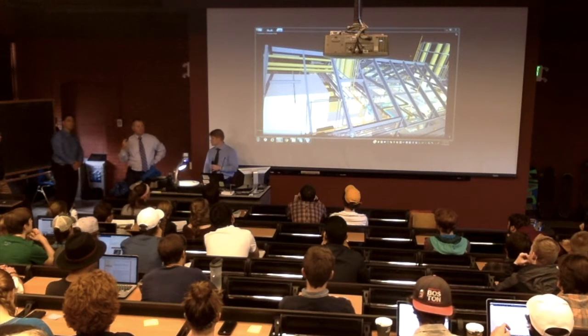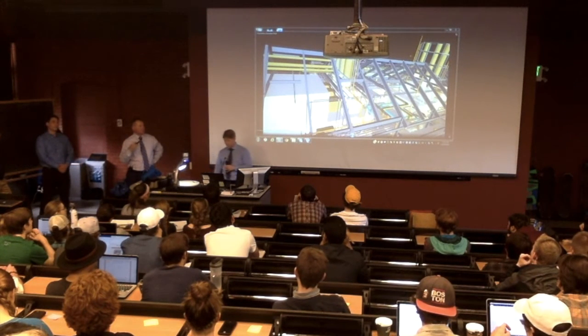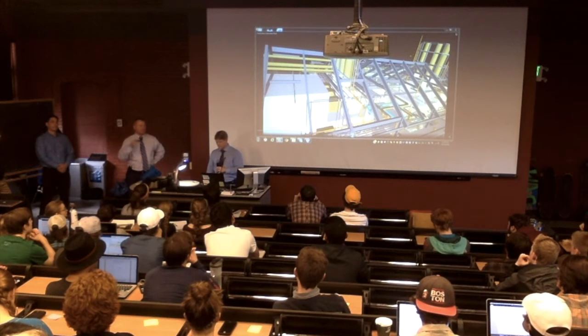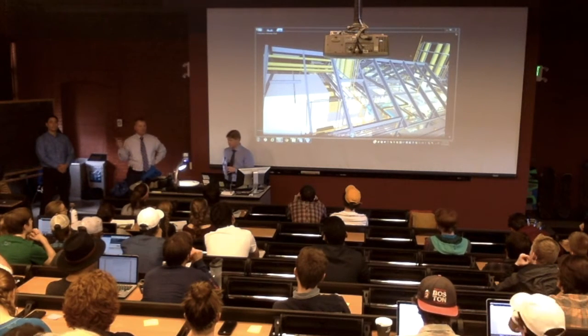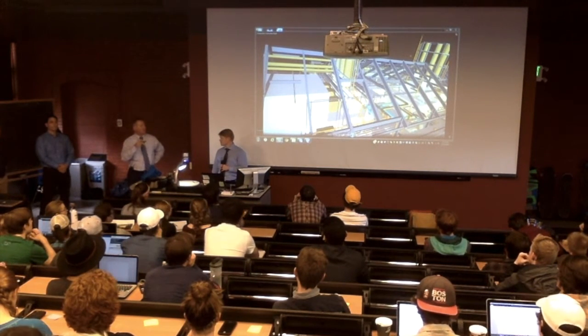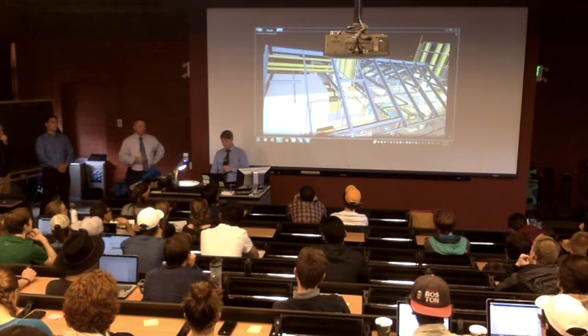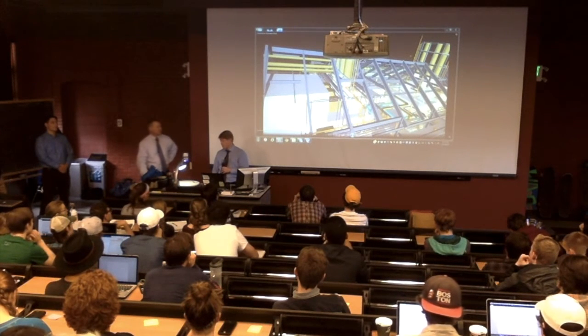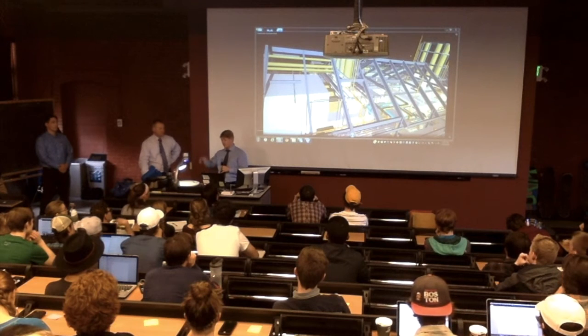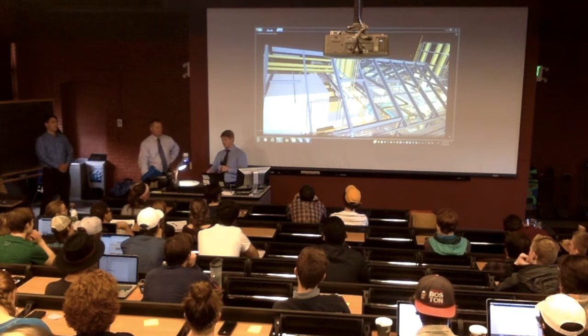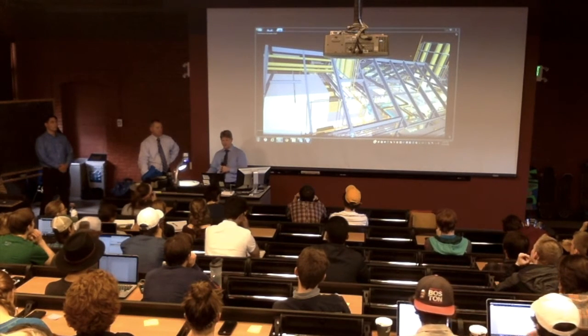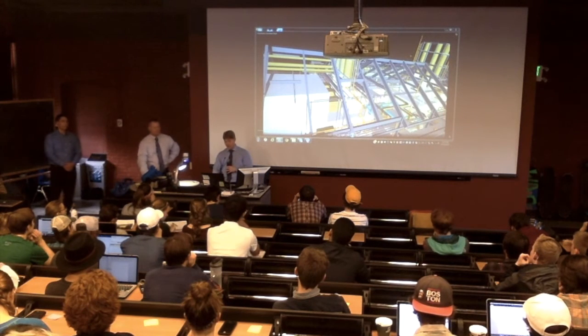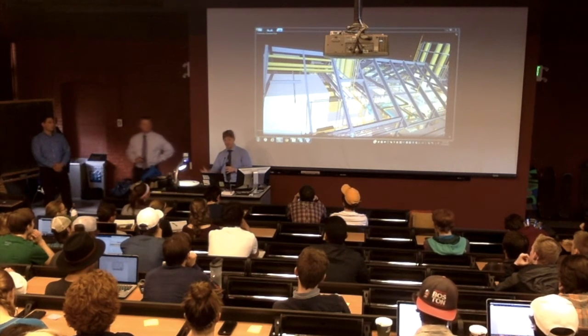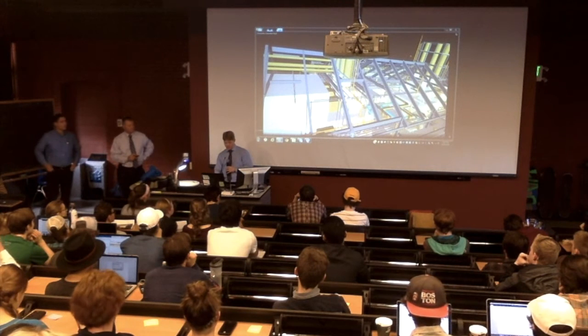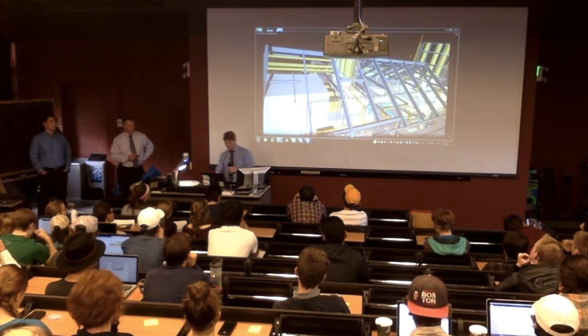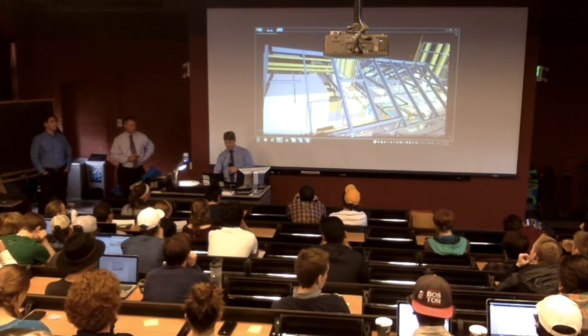Alex mentioned it earlier, there's a consultant that actually looks at the airflow, the velocity of the wind in the area and the topography to figure out how tall those need to be. So it's another branch of engineering that's out there. Yeah, they actually will build a model of the campus. They didn't in this particular case, but they will to get real detailed actual wind analysis of how that affects what comes out of the stacks. They also can use computer fluid dynamics to be a little bit easier method of accomplishing that.